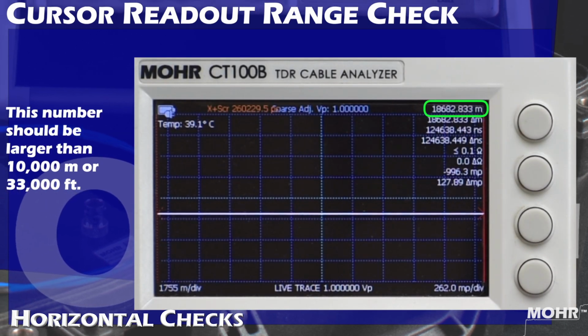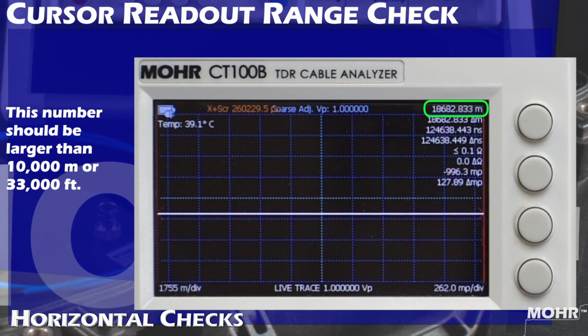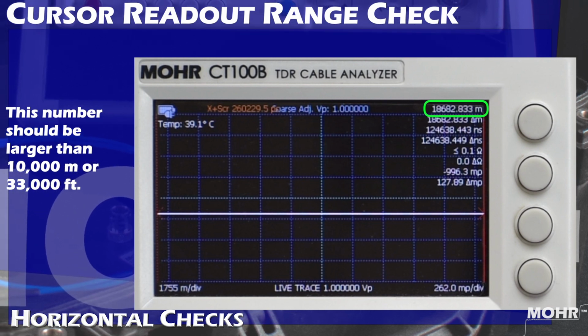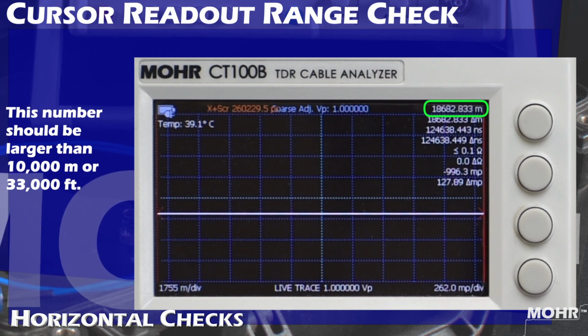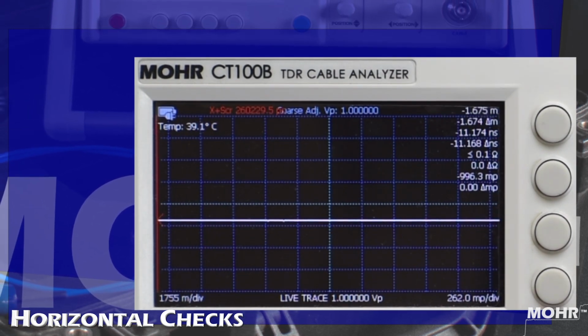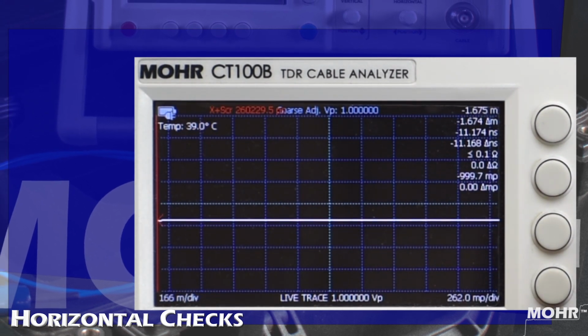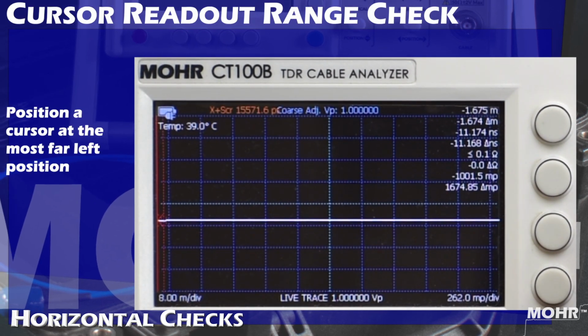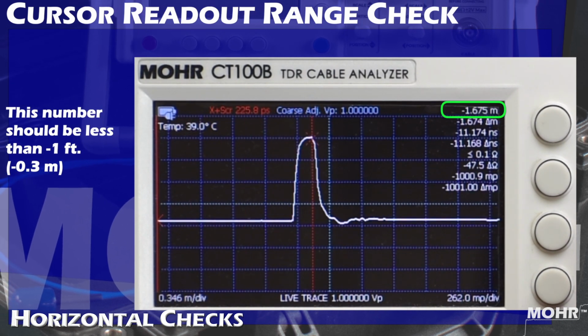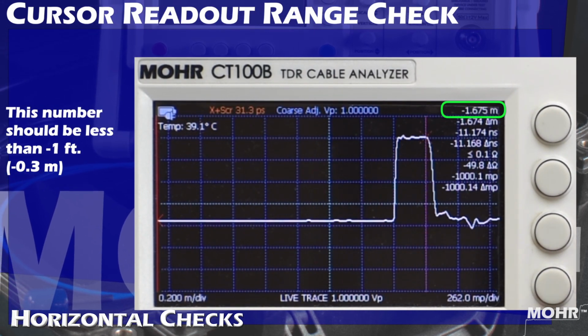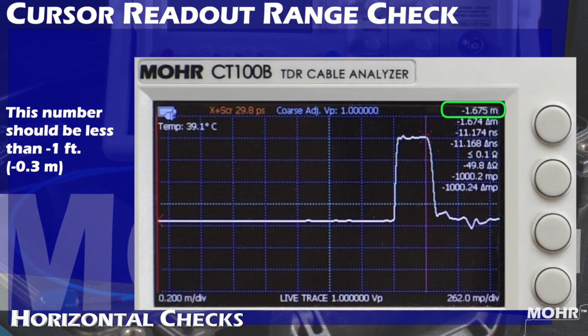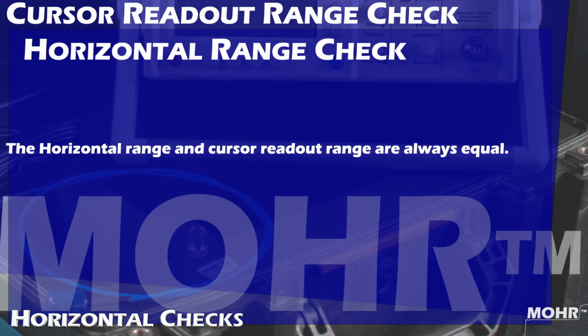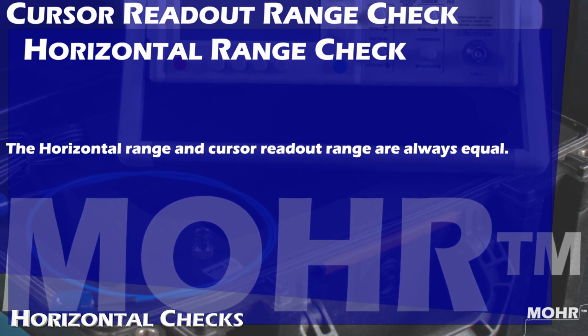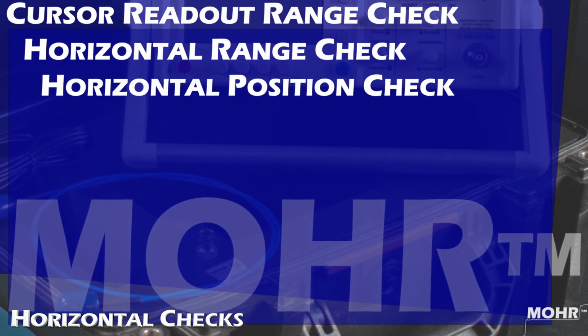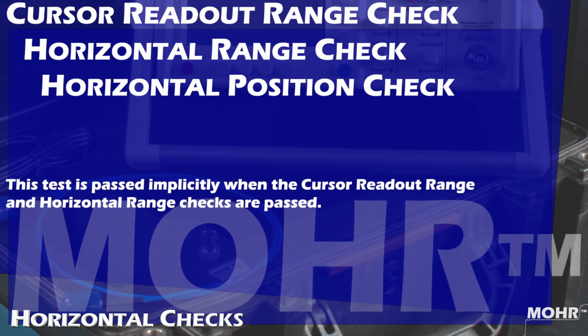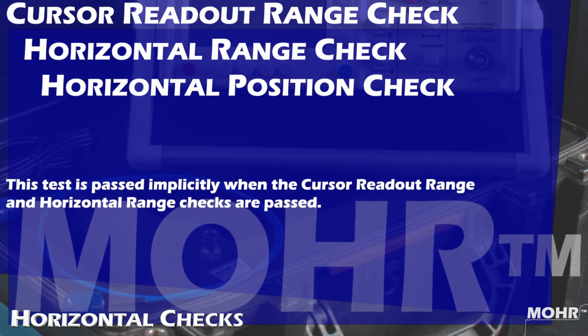The absolute distance measurement for the cursor is the upper limit for the cursor readout range. This number should be larger than 10,000 meters or 33,000 feet. Now we're going to position a cursor at the far left position. The absolute distance measurement for the cursor is the lower limit for the cursor readout range. This number should be less than -1 foot or -0.3 meters. For the horizontal range check, the horizontal range and cursor readout range are always equal.